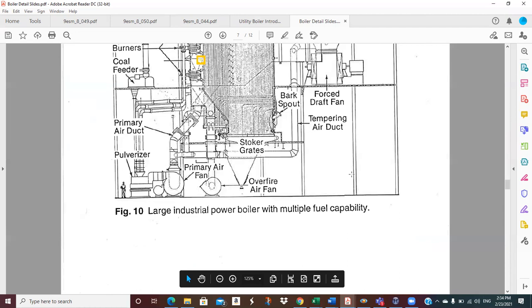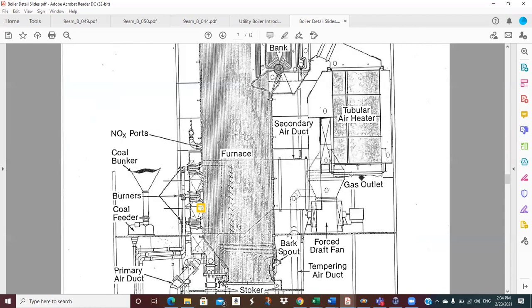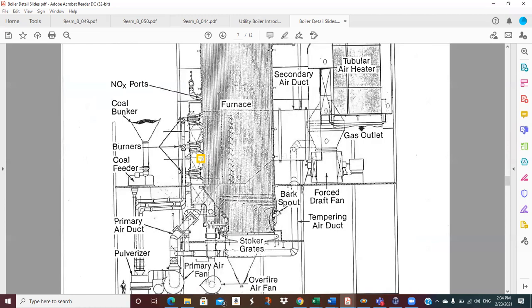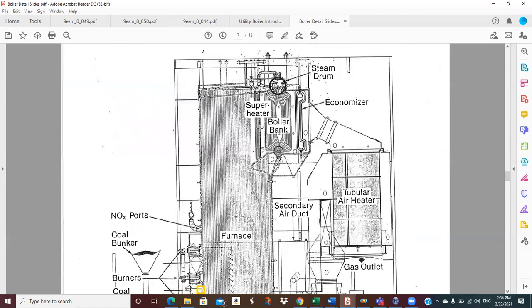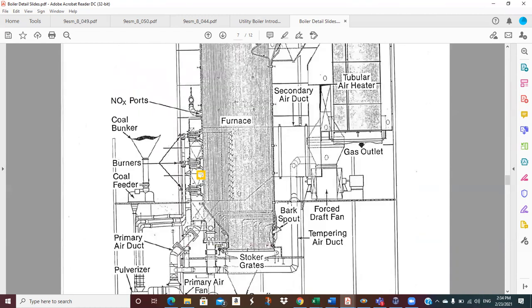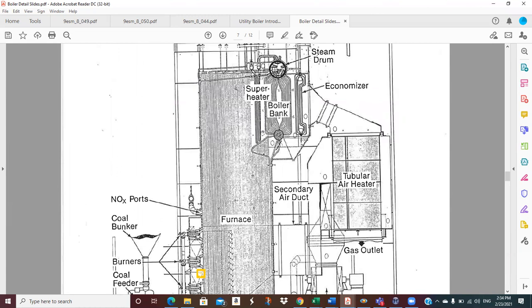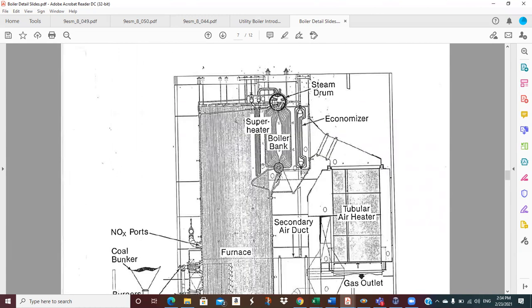I don't know. This is a large industrial power boiler. What you see is a lot of it is fairly common. I mean, it gets simpler, but you don't have very much superheating capability. You see the relative amount of tubes over here in the furnace. This is water wall, and that's all steam generation feeding in here. We show a small superheater section, so this boiler could do a little bit of superheating, but not much.